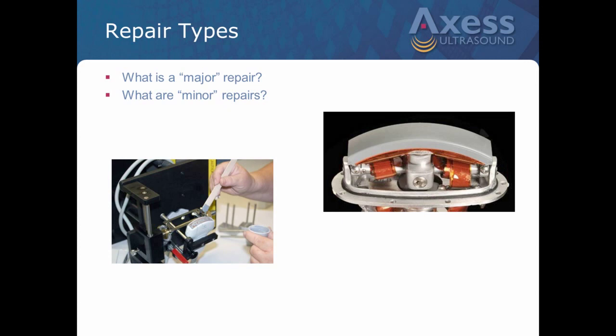A retermination, essentially, what happens is the individual tiny coax wires that attach to the array itself will break, they'll fray, they'll lose contact. So what we do is we have to go in and cut them back, reterminate them to the array. And again, you're talking about anywhere from 64 individual coax wires on a transesophageal probe to maybe 256 on a multiplexed linear probe. So it is a tedious task.